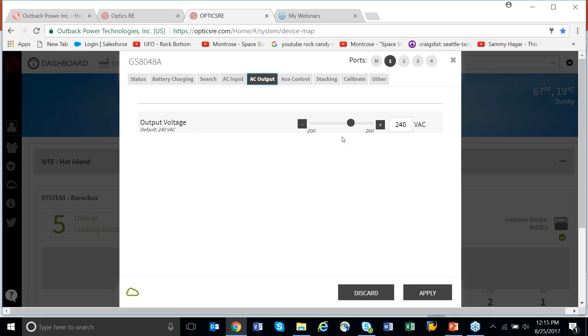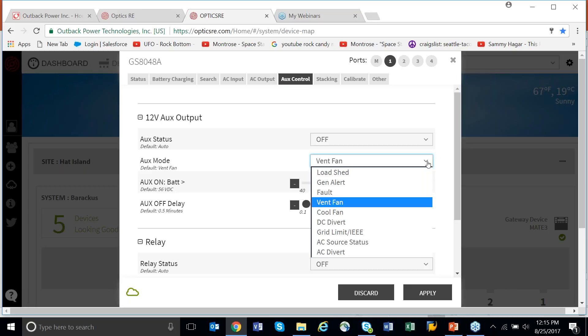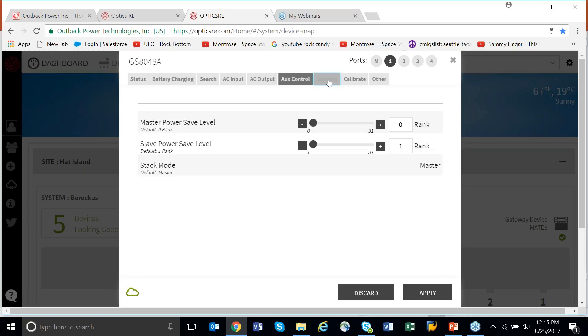AC output lets you calibrate and set basic voltage output. Aux control allows you to turn it on or off, make adjustments to the vent fan, and choose the aux mode you'd like. Under stacking, we don't let you actually do the stacking, but you can adjust the power save level and the ranking. Stacking is a hardwired condition, and if you try to change it without changing the wires you can damage the gear, so we don't allow stacking adjustment — but you can adjust power save.